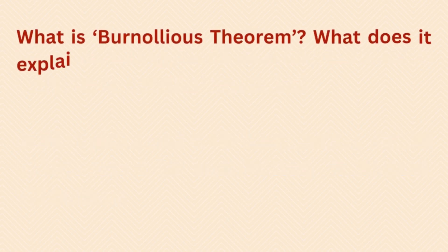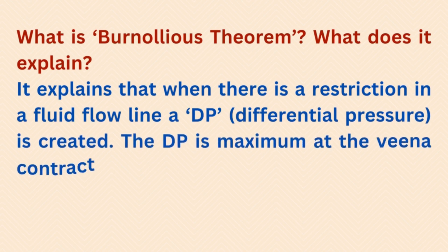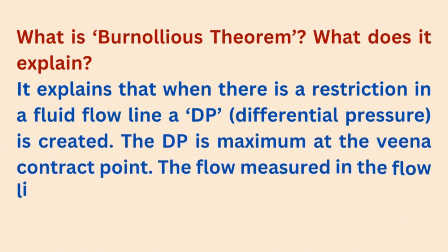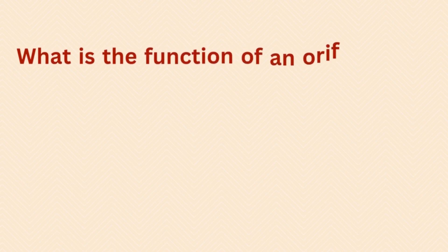What is Bernoulli's theorem and what does it explain? It explains that when there is a restriction in a fluid flow line, a differential pressure (DP) is created. The DP is maximum at the vena contracta point. The flow measured in the flow line is proportional to the square root of the DP measured, where k is a constant.